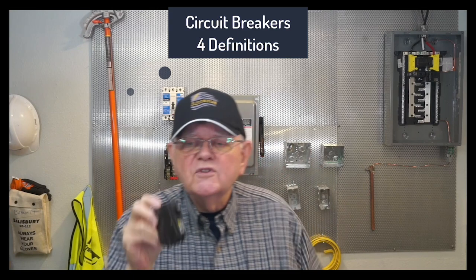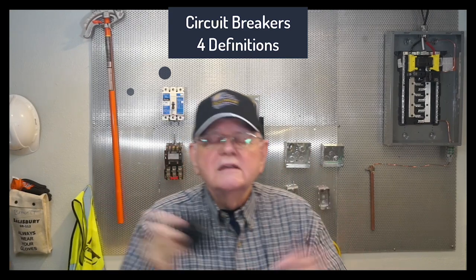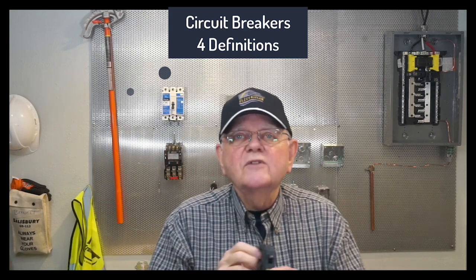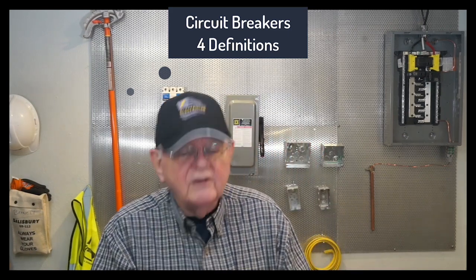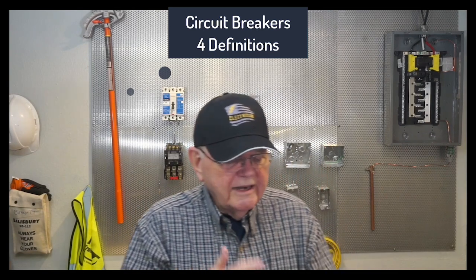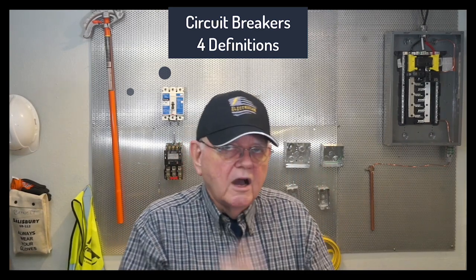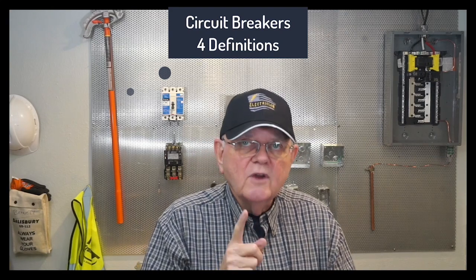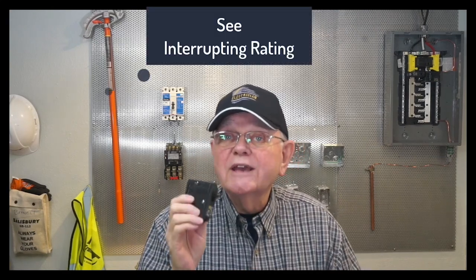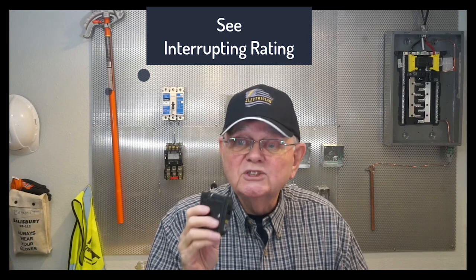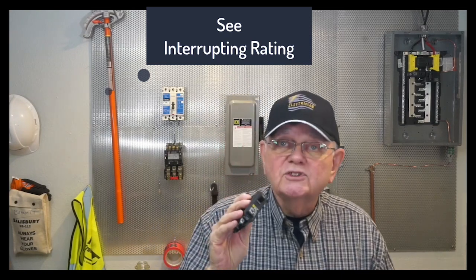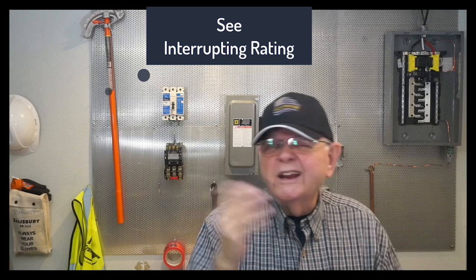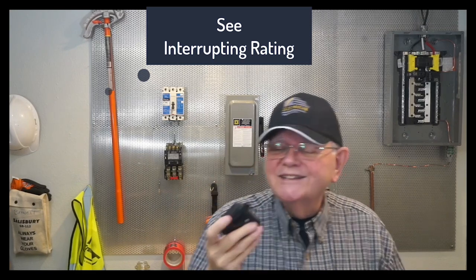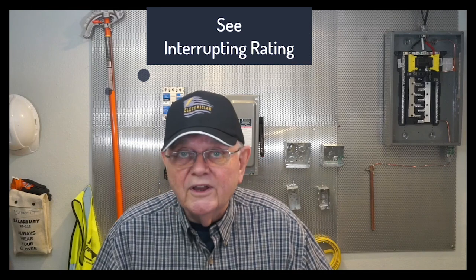So 20 amps is what's on the handle, meaning that it's rated to continuously carry up to 20 amps of current flow. I don't want to exceed any temperature limitations on the breaker. It gives me the type breaker. It has an interrupting rating of 10,000 amps. Interrupting rating: how much current can this breaker open up under a fault condition and not have any physical damage to it? Okay? That's my interrupting rating, kind of in a nutshell, if you look at the definition in the NEC for interrupting rating. So this is an inverse time circuit breaker.